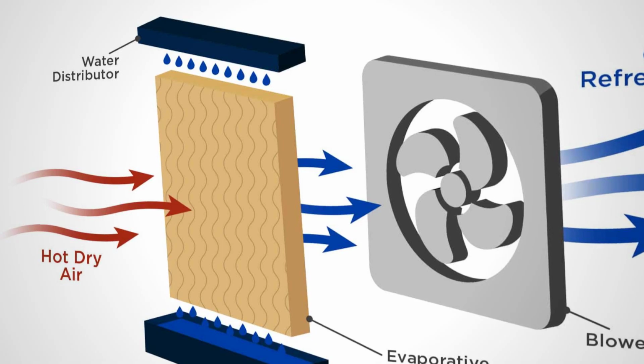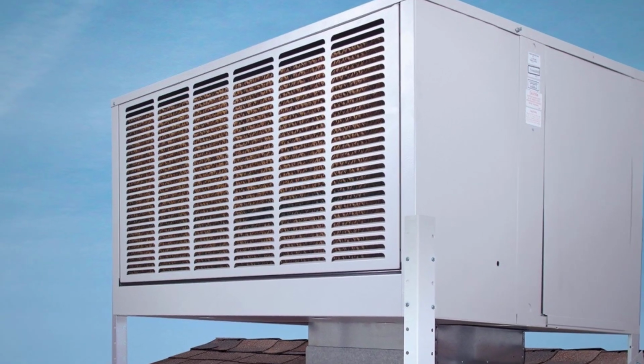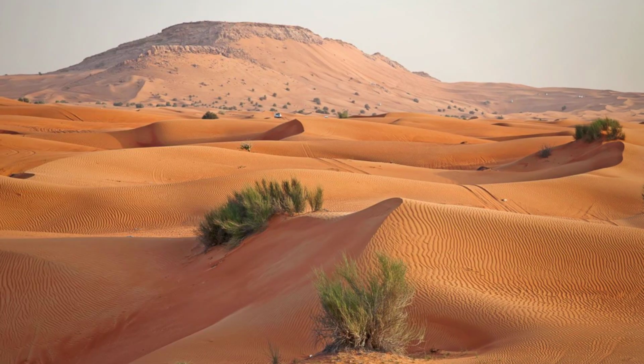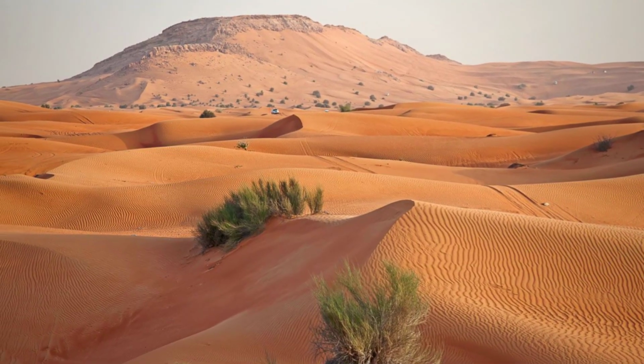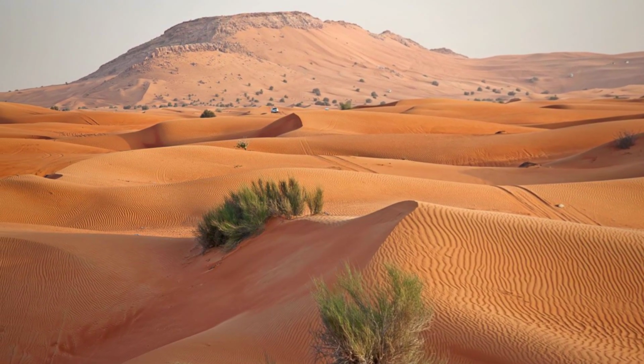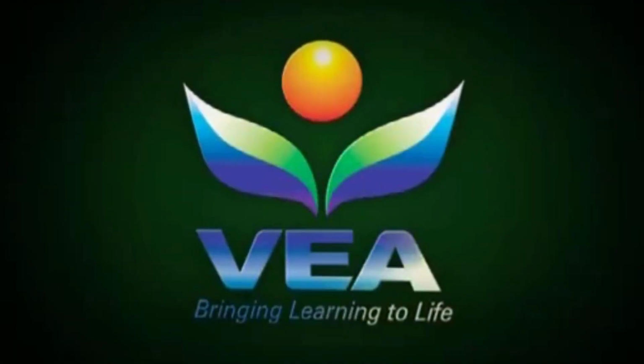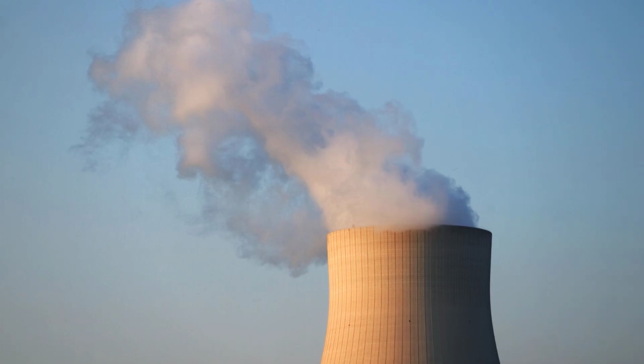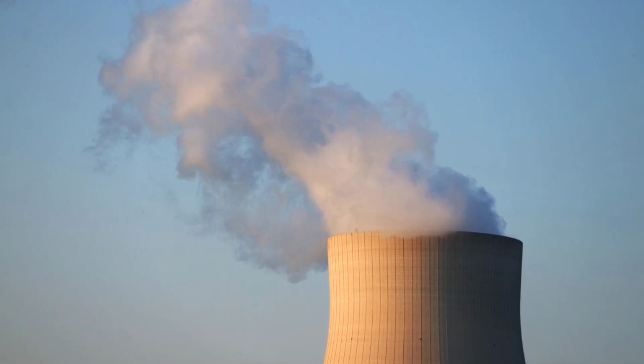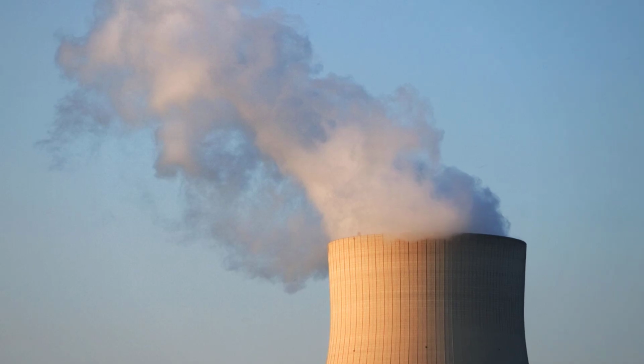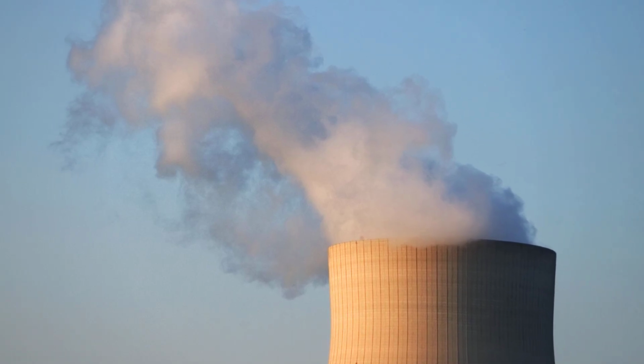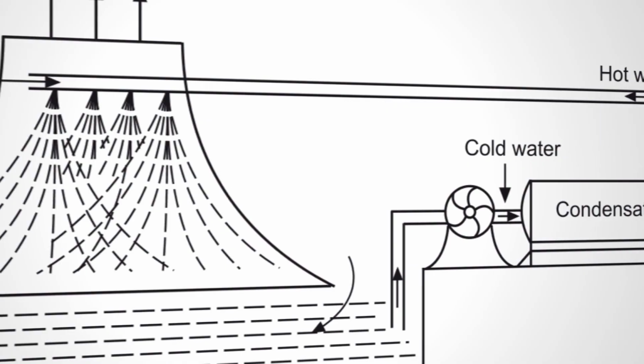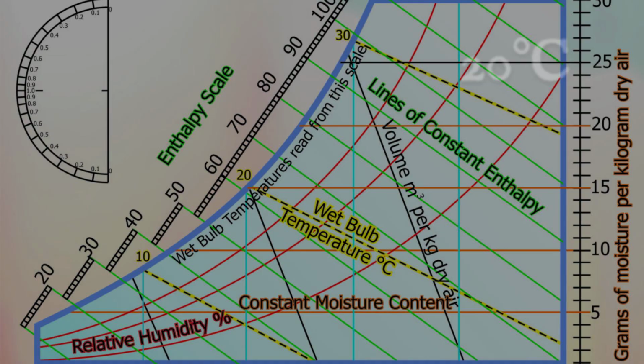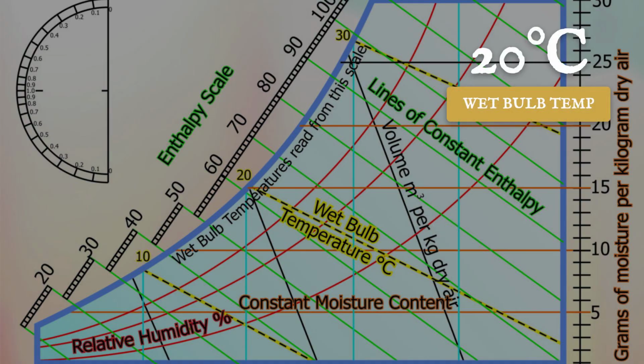In dry climates, you might be familiar with evaporative coolers, sometimes called swamp boxes, which cool and humidify the air. It makes sense that these work better in dry climates, as less moisture in the ambient air allows for more evaporation and thus greater cooling potential. Therefore, one might assume natural draft towers perform best in areas with low relative humidity, but that's not necessarily the case. This concept took some effort to grasp. Let's revisit that psychrometric chart.